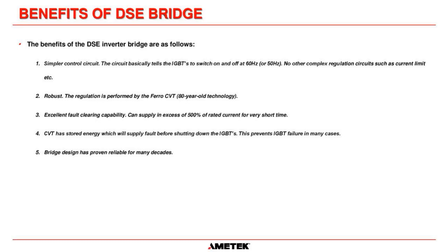The DSE has excellent fault clearing capability due to the constant voltage transformer. It can supply in excess of 500% of the rated current for a very short time into a short circuit. The CVT has stored energy, which will supply the fault with the necessary current to clear the fault usually. It also allows us, while the transformer is supplying that high current, to shut the IGBTs down. Remember, IGBTs are very sensitive to high current—the transformer will supply the current, so we can shut the IGBTs down before they see that high current, which helps prevent IGBT failure in most cases.